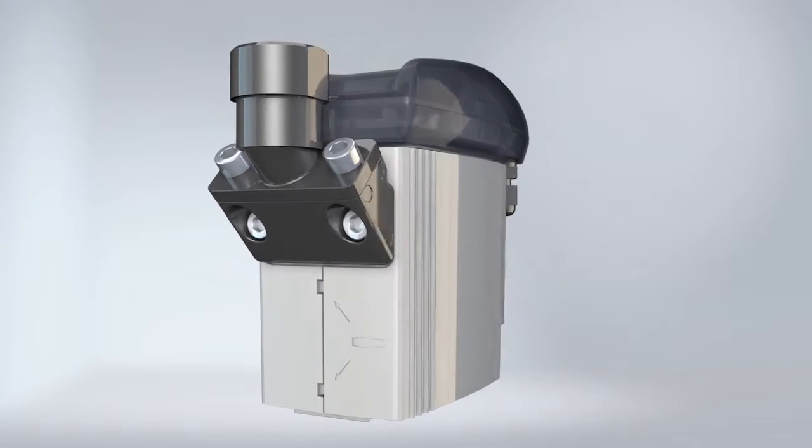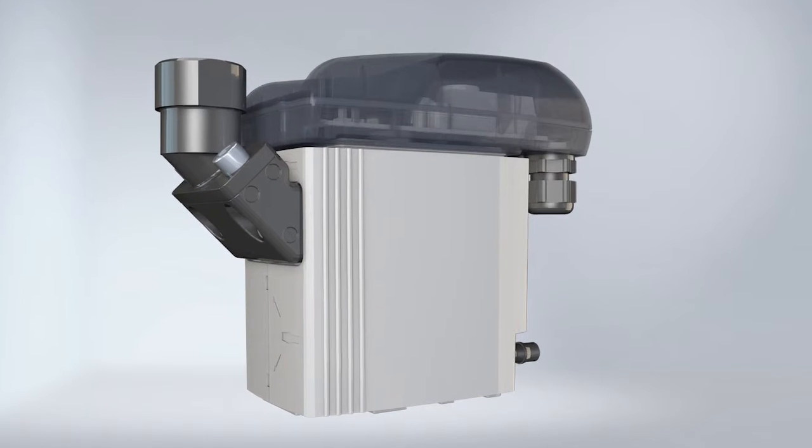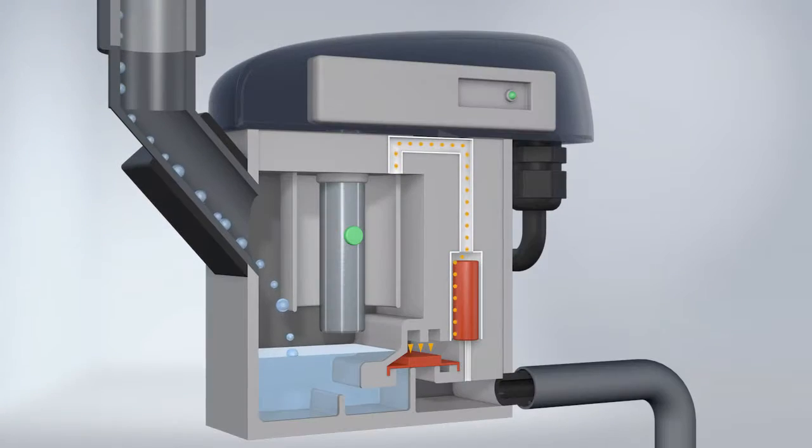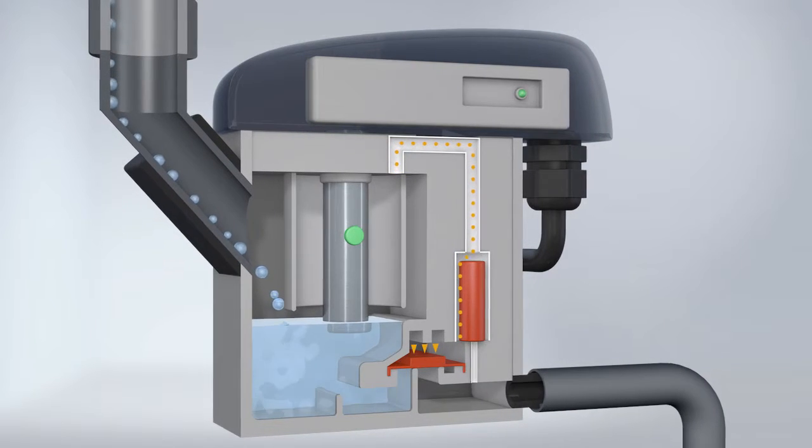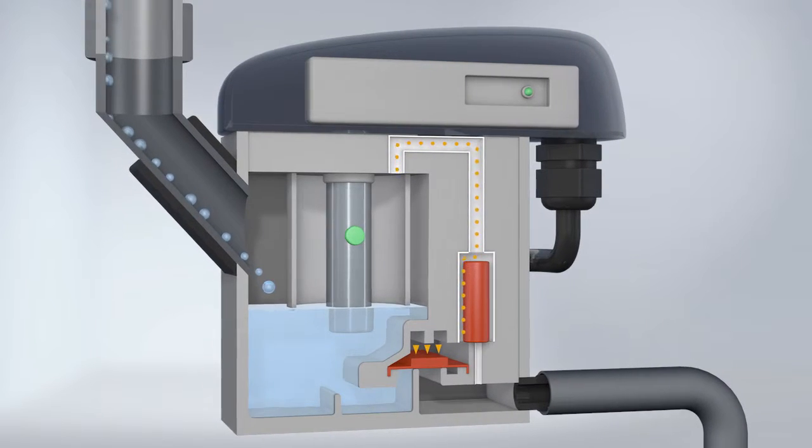But exactly how does it work? Adapted to the amount of condensate and without compressed air loss, condensate flows in via the feed line, whilst air pressure from the vent pipe keeps the membrane closed from above.